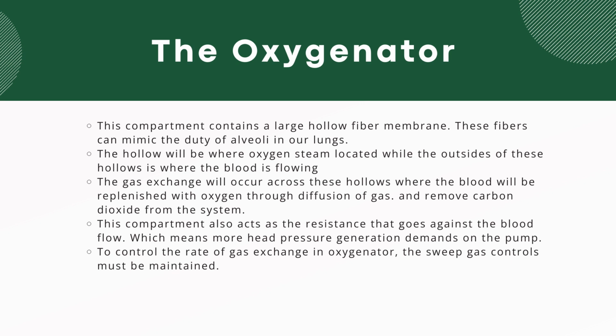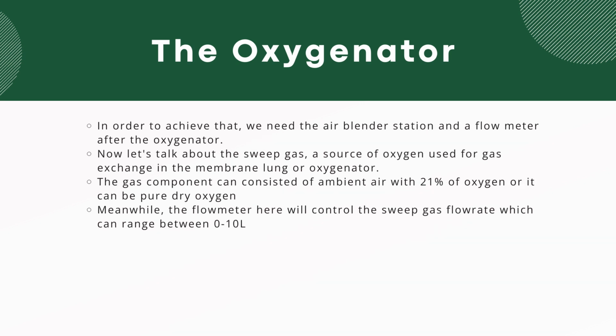This compartment also acts as a resistance against the blood flow, which means more head pressure generation demands on the pump. To control the rate of gas exchange in the oxygenator, the sweep gas control must be maintained. In order to achieve that, we need the air blender station and a flow meter station after the oxygenator. Now let's talk about the sweep gas. The sweep gas is a source of oxygen used for gas exchange in the membrane lungs, or oxygenator. The gas component can consist of ambient air with 21% oxygen, or it can be pure dry oxygen. In other words, the sweep gas allows for removal of carbon dioxide in an efficient manner. Meanwhile, the flow meter here will control the sweep gas flow rate, which can range between 0 to 10 liters per minute.